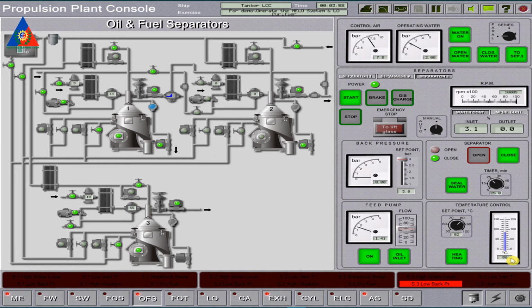Check the required lube oil temperature. The product pressure at the lube oil outlet or back pressure is controlled with the aid of set point bar controller. If water lock is broken because of the high back pressure, it is necessary to reduce the back pressure by 0.5 to 1 bars and or to decrease the fuel feed.